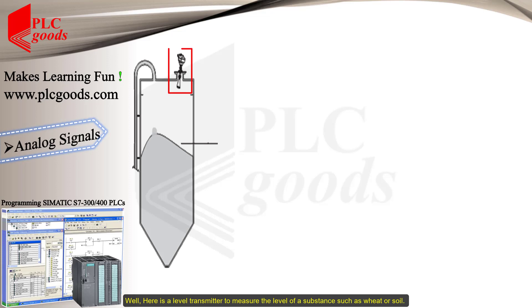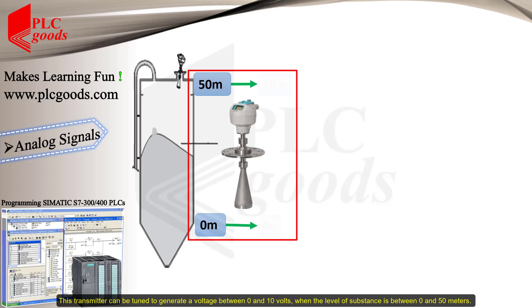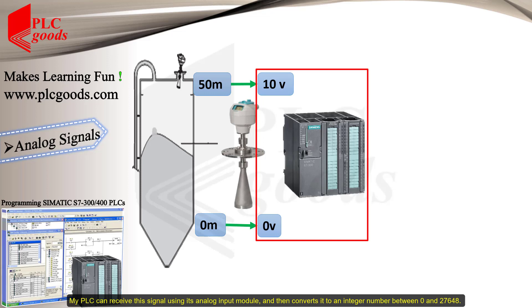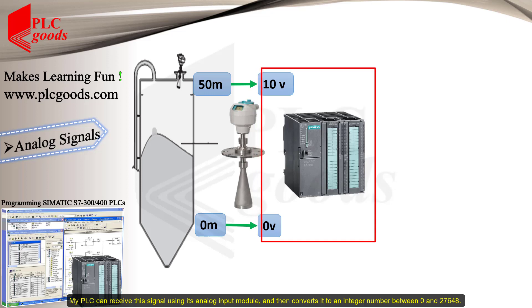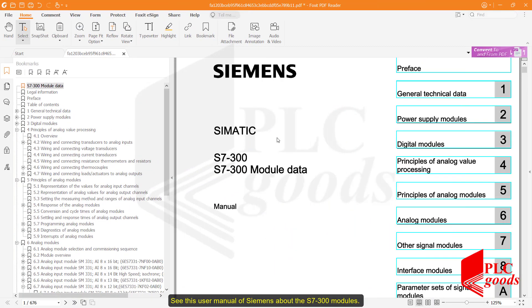Here is a level transmitter to measure the level of a substance such as wheat or soil. This transmitter can be tuned to generate a voltage between 0 and 10 volts where the level of the substance is between 0 and 50 meters. My PLC can receive this signal using its analog input module and then convert it to an integer number between 0 and 27,648. We need to use the user manual of each PLC brand to find these numbers. Let's select chapter 4: Principle of Analog Value Processing.